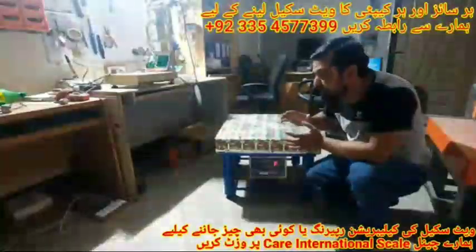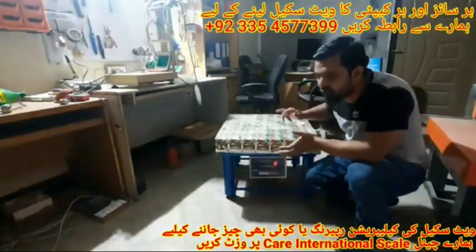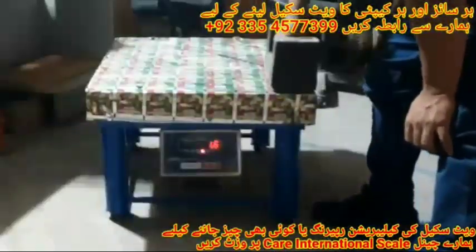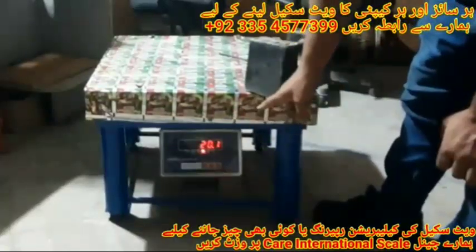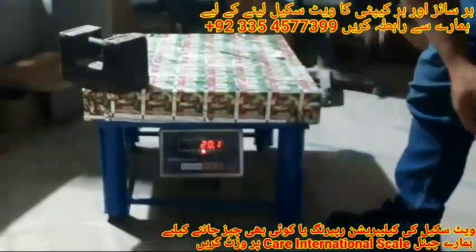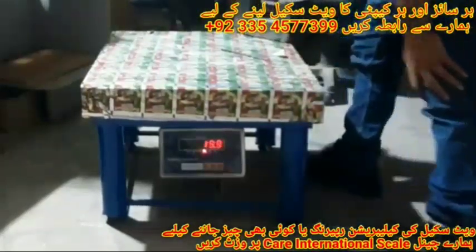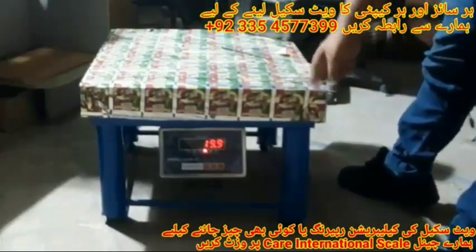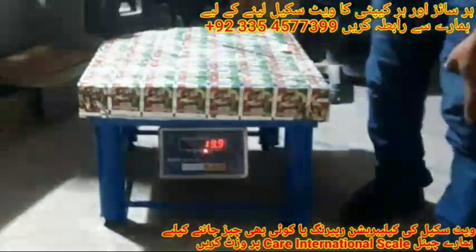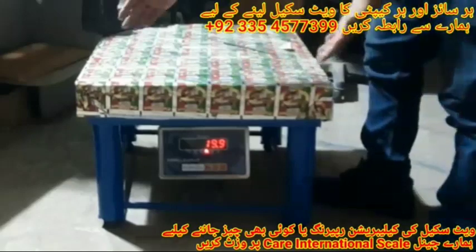The weight is different in the four corners, so today we will talk about cornering. We have a 20 kg dead weight and we will place it in all four corners of the platform to check whether it gives correct weight or not. First corner shows 20.1 kg, second corner shows 20.1 kg, third corner shows 19.9 kg, and fourth corner shows 19.9 kg.